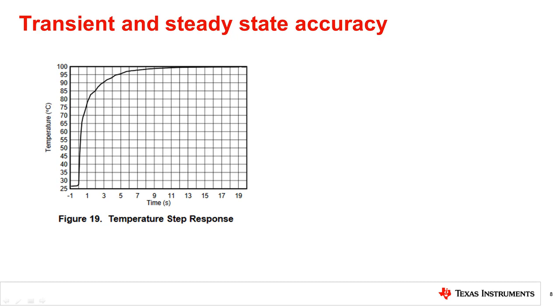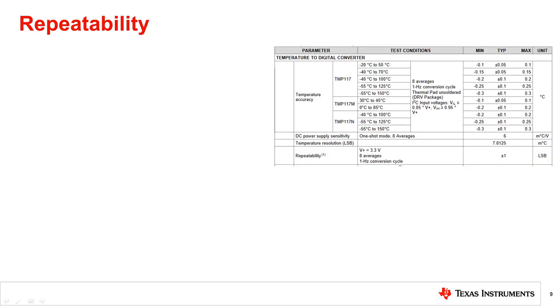When the time constant of the reference is much shorter than the sensor, a measurement may result in negative error. Similarly, if the time constant of the reference is much longer than the sensor, a measurement may result in positive error. Thus, in order to compare the accuracy of the measurement system to the reference, the thermal step response of both the reference and measurement system must be taken into account. We have now reviewed the various sources of error outside of the sensor itself, including the measurement system, operating environment, and measurement conditions, and how to isolate each of them.